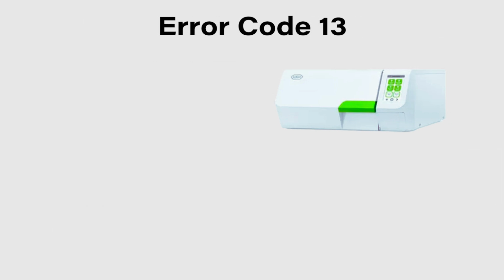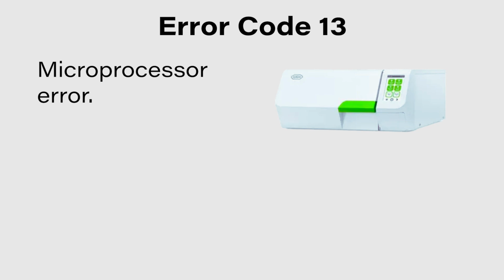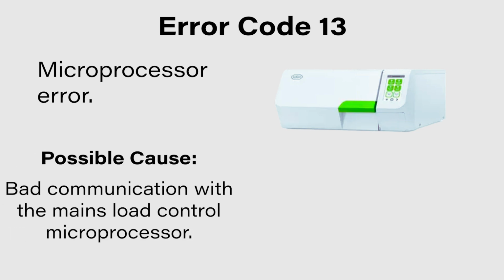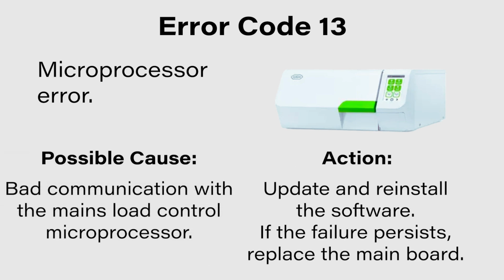If your W&H Lexa Mini Autoclave is displaying an error code 13, that means there was a microprocessor error. The possible cause is bad communication with the mains load control microprocessor. For this, update and reinstall the software, and if the problem persists, replace the main board.